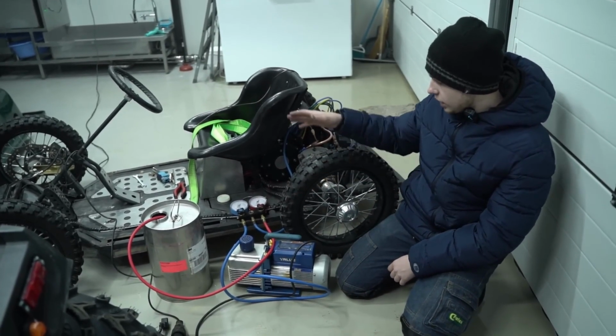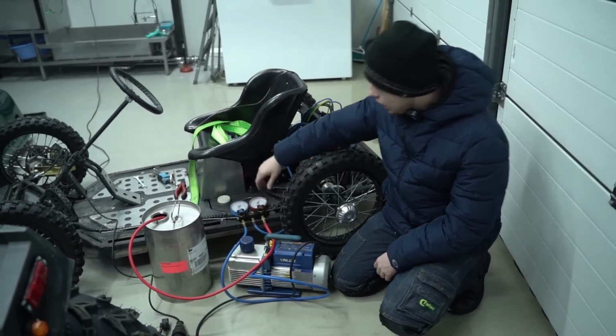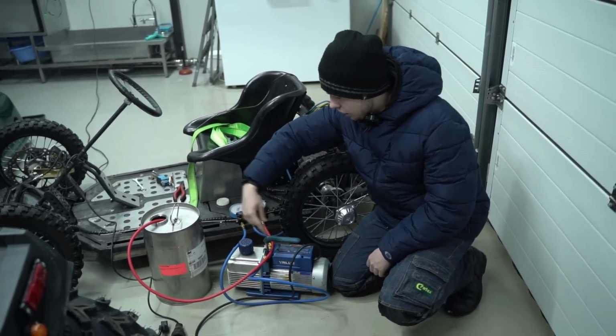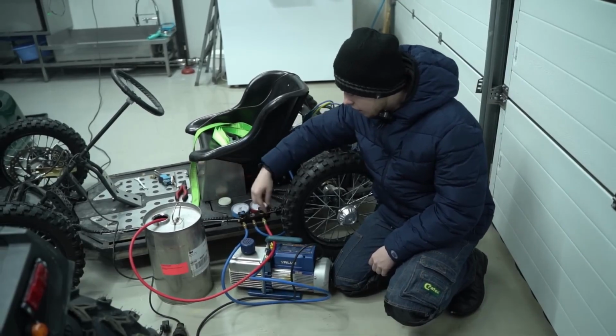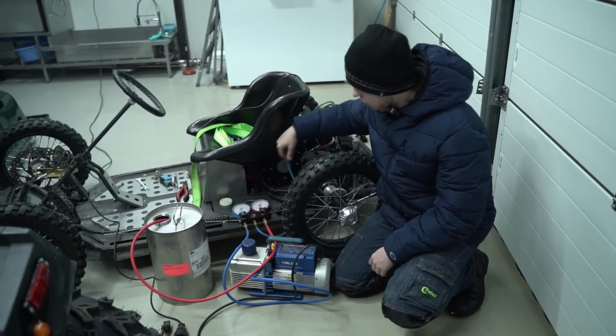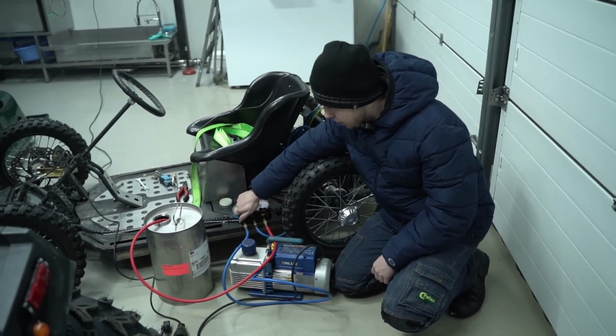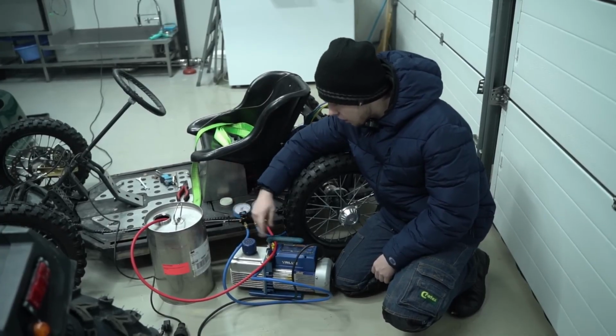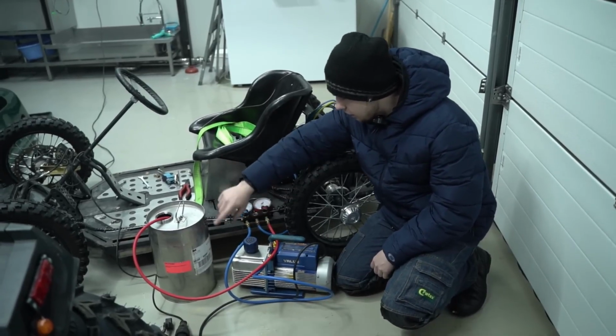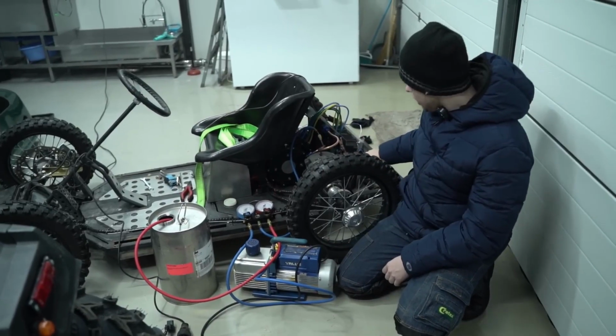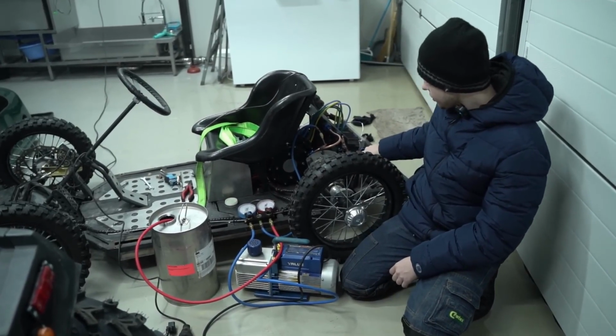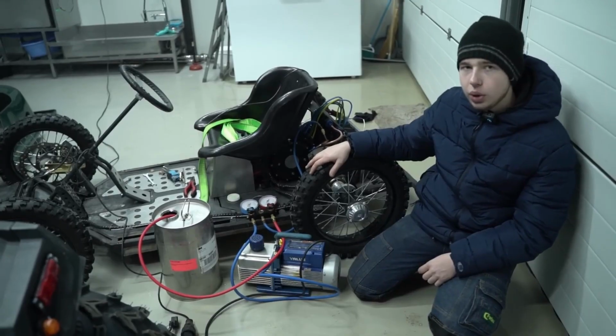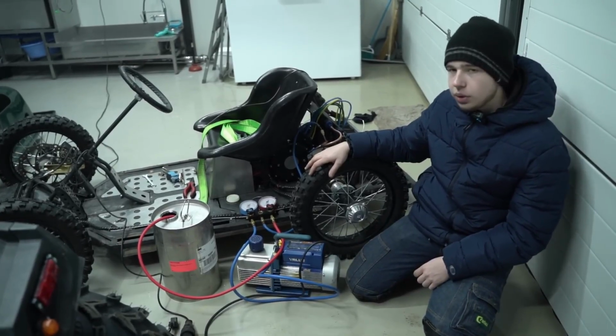As I've already mentioned, after the initial vacuuming process, a small amount of liquid inevitably passed through the connecting hose. After we fully vacuumed the entire system, we carefully close off the vacuum line from the main pump, then open the liquid pump valve, and watch through the transparent sight glass to precisely determine how much liquid we actually need to fill into the system.